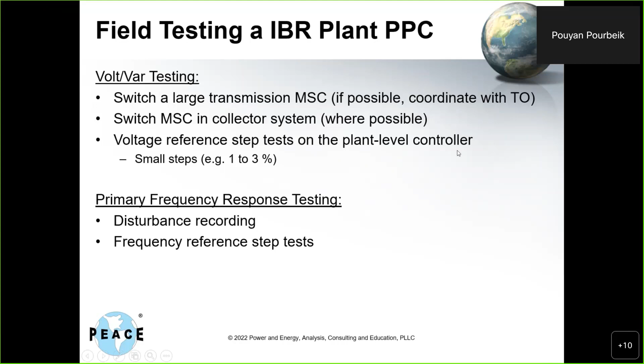So here are examples. An example of doing a voltage reference step test - it looks good. Here's an example of doing it coordinated with the TO: there was a significantly large transmission capacitor close to the point of interconnection of three plants, and they switched it in. You can see all three plants' megawatts, megavars, and voltage, and you can even go down and look at the individual turbine stuff, and it all seemed to behave well.